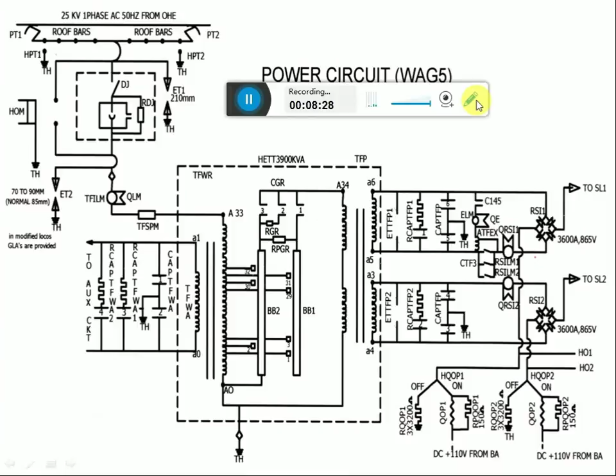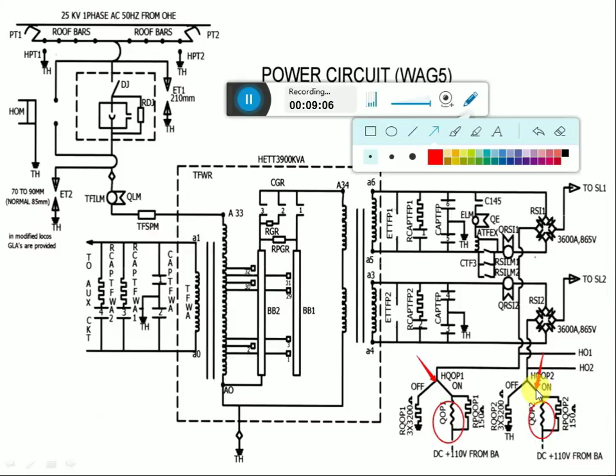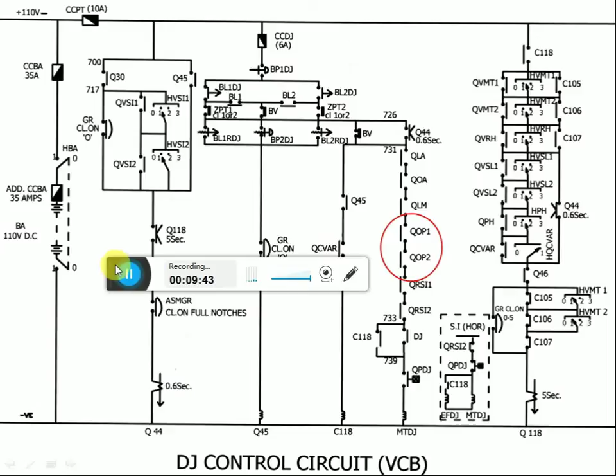QOP1 is connected to traction power circuit number 1. It was connected between TFP1 negative winding and battery through a switch HQOP1. Similarly, QOP2 is connected to the traction power circuit number 2 negative cable and to the battery through a switch HQOP2. In case of any earth fault in traction power circuit number 1 or 2, the concerned relay, QOP1 or QOP2, will energize. Their normally closed interlocks will open on the MTDJ branch and DJ will trip. Loco will be protected from earth fault.